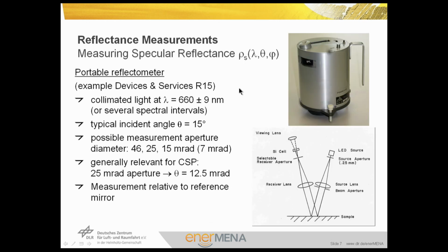For reflectance measurements of the specular reflectance, there are several instruments that can be used. Typically in this area, we use, for example, the Devices and Services R15 reflectometer because it has proven to give repeatable measurements.